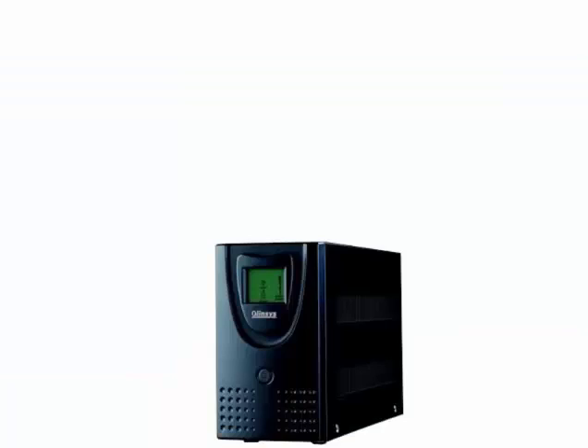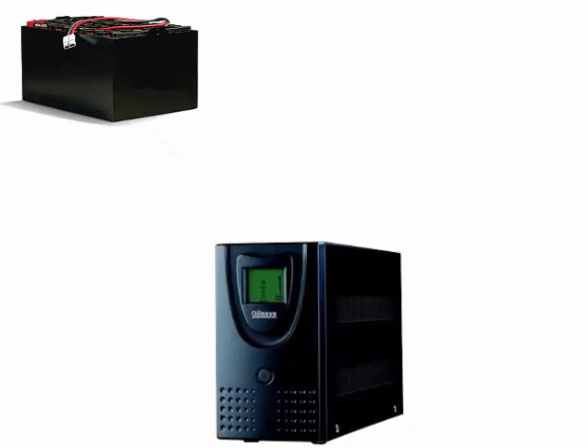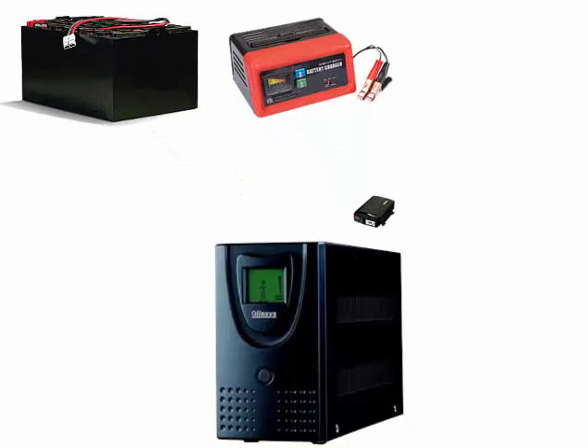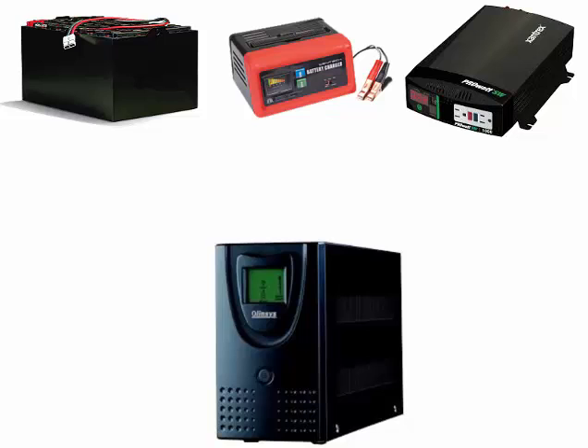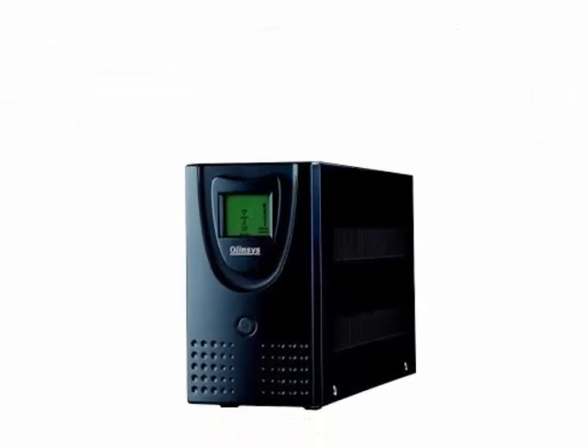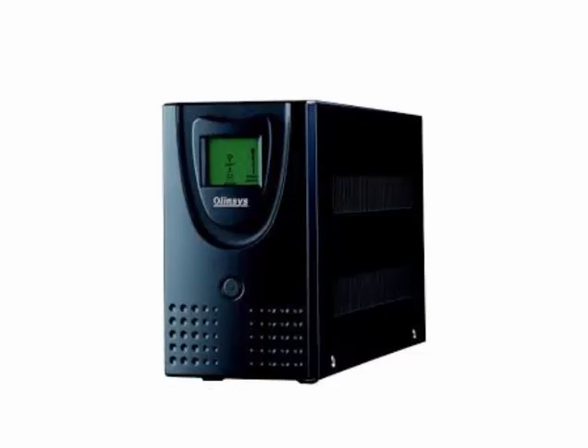A typical UPS is comprised of a battery bank, a battery charger, and an inverter with a way to switch the load between grid power and inverter power in case of grid power failure. There are many types of UPS configurations pertaining to the load switching mechanism. The most prevalent nowadays is the line interactive and standby types, especially in small power ratings. Standby isn't the best option regarding load switching speed, but it is the simplest, so we'll start with it.